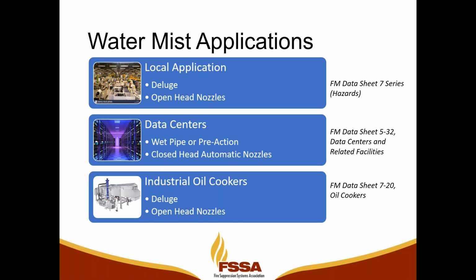We also have industrial oil cookers, and this one sometimes surprises people. People grow up thinking water and oil don't mix, never throw water on a grease fire because you'll spread it all over your kitchen. And that's very true for homeowners. That is not true at all with industrial oil cookers. Water is a fantastic agent for this application, as is CO2. We do see people retrofitting oil cookers from CO2 to water mist for life safety reasons.